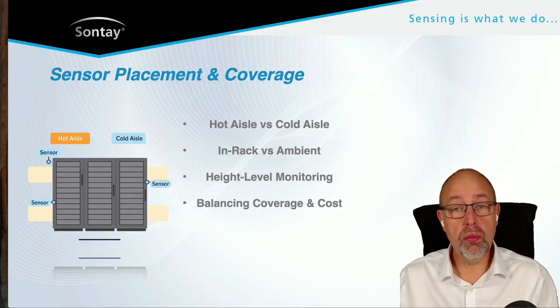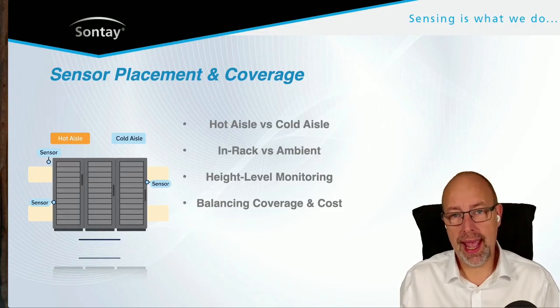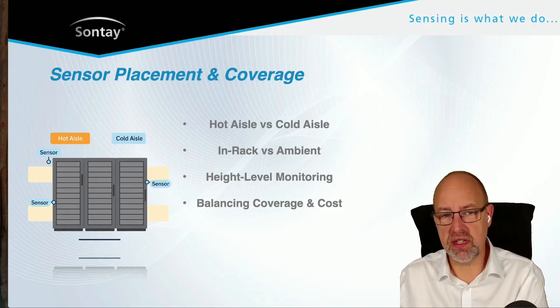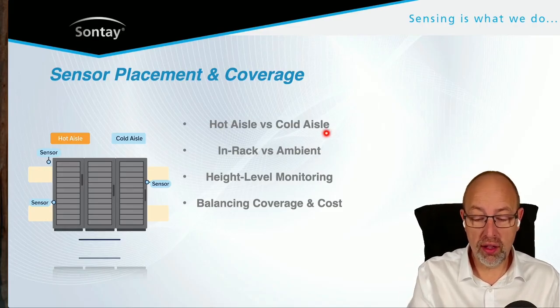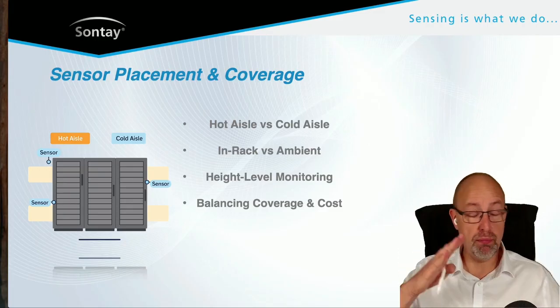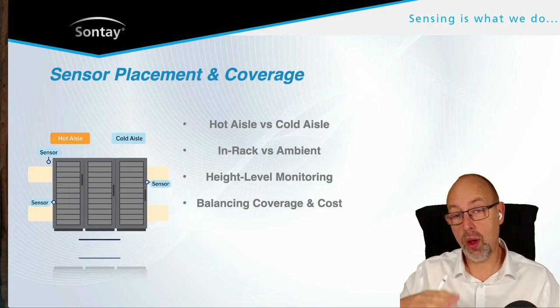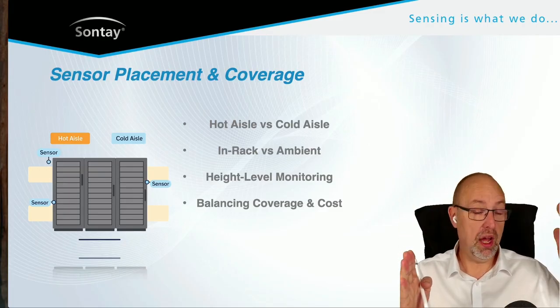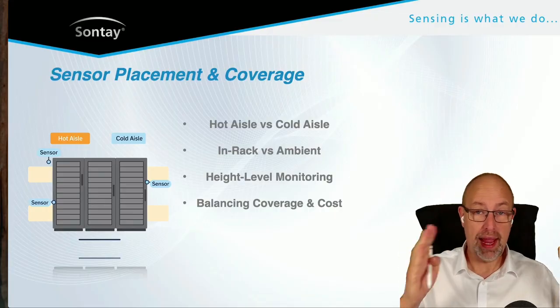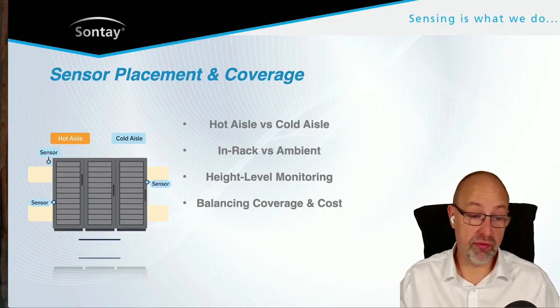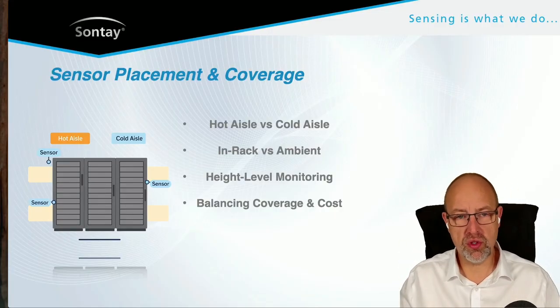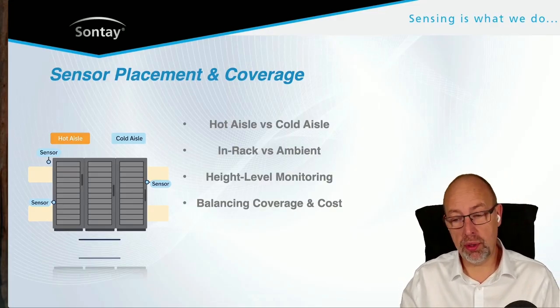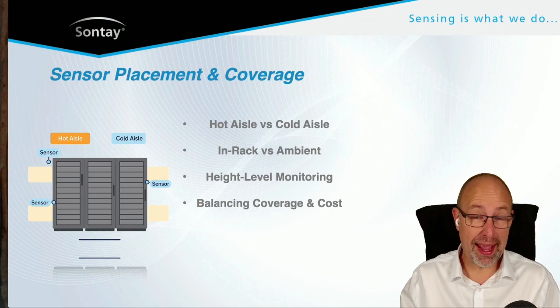In terms of what you might want to sense, you're often looking at delta temperatures, differences in temperatures. We've got hot aisle versus cold aisle - what is the temperature difference across the racks? So you have cold aisle monitoring and hot aisle monitoring. How much heat is a server or a rack putting out? What are those temperatures, and what should they be?